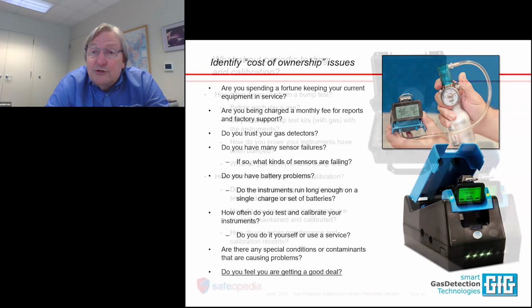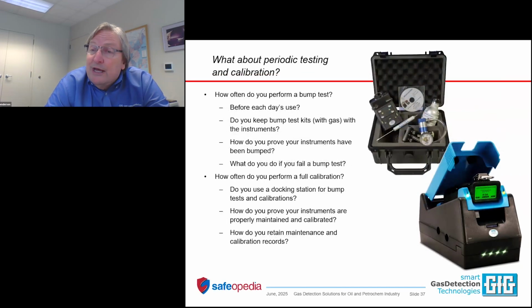And remember, you're expected to maintain that instrument according to manufacturer requirements. So whatever the manufacturer says in the manual, that's your burden. That's your obligation. And when it comes to periodic testing and calibration, OSHA is pretty firm. The NFPA is equally firm. CSA and UL are also very firm in their recommendations or requirements. You're supposed to perform at a minimum a qualitative bump check before each day's use. That's simple to do. It's just exposing the sensors in the instrument to gas above the initial alarm concentration. And when you flow the gas, you make sure that the alarms are activated.